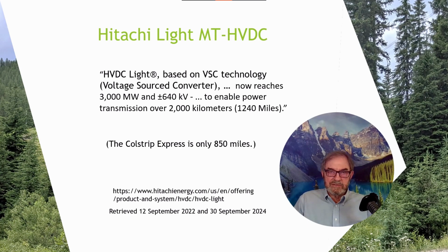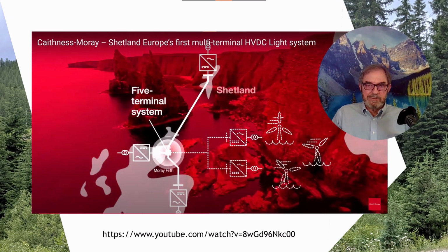The last 2 years, these MT-HVDC systems have been available at up to 3,000 megawatt at plus or minus 640 kilovolt to enable power transmission over 1,240 miles. The Colstrip Express is only 850 miles. This was Europe's first multi-terminal HVDC system. Stage 1 of the Colstrip Express will also have a 5-terminal system, including 2 wind farm terminals.